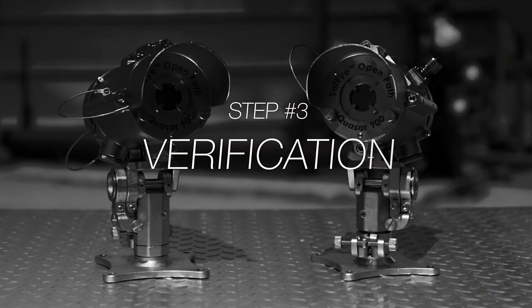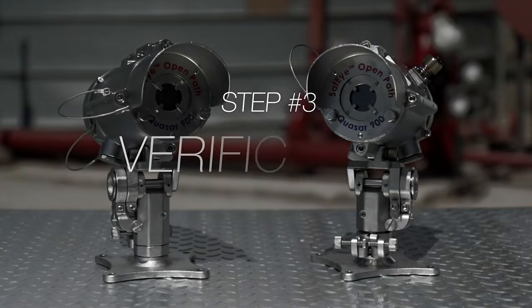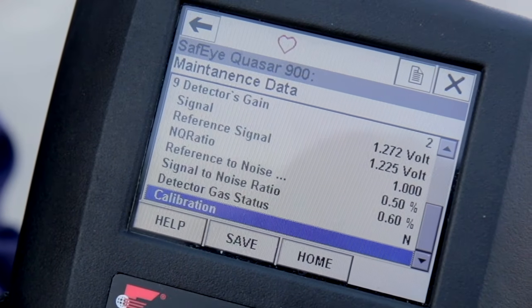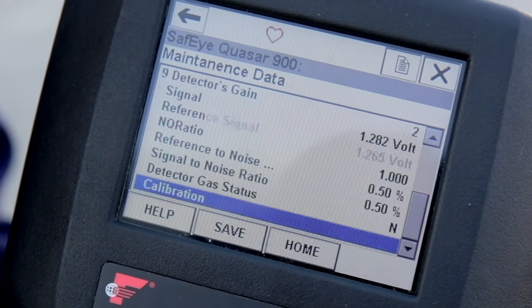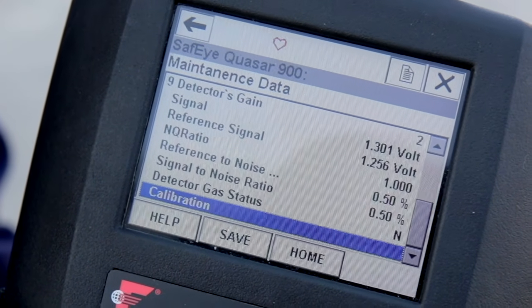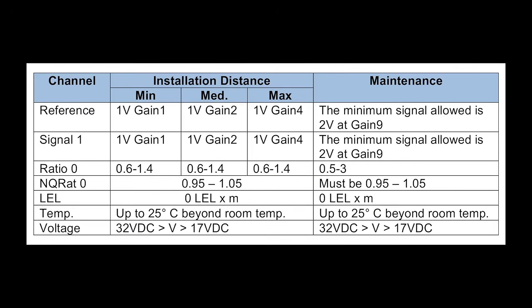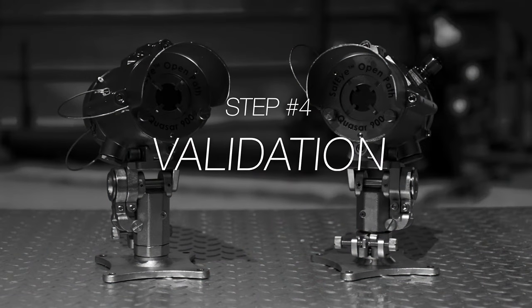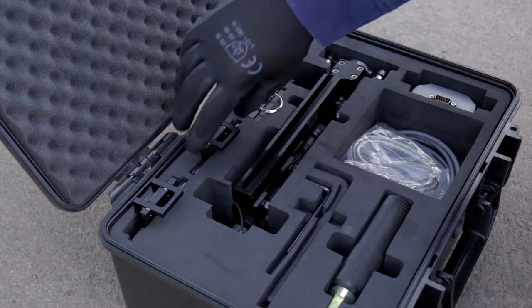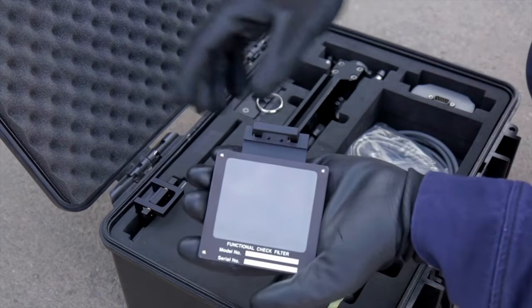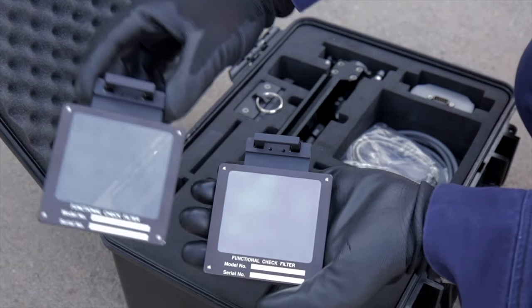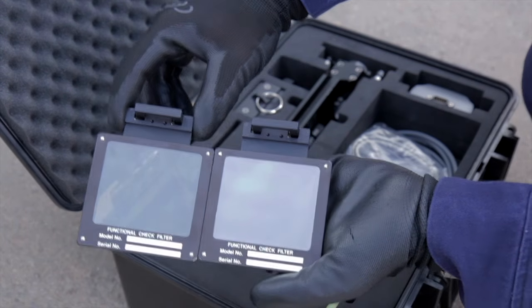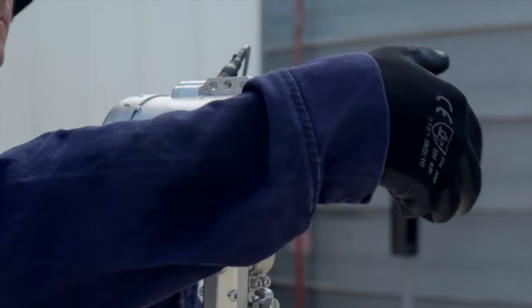Now let's move to the verification stage. On the HART maintenance screen, you should verify that the signals are within the specific range per the signal values table listed in the manual. We recommend to record these values to compare at your next periodic maintenance check. Step 4. Validation. The last step is to validate the system functionality by using the functional check filters in the HART handheld unit. First, position the functional check filter in front of the detector.